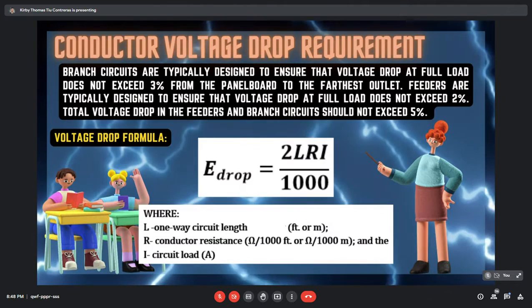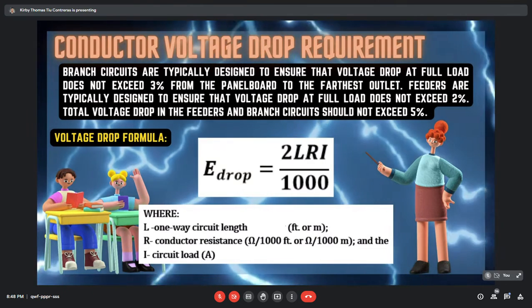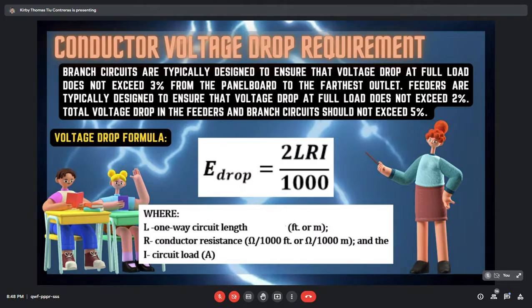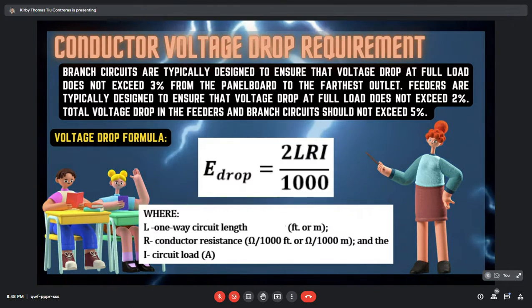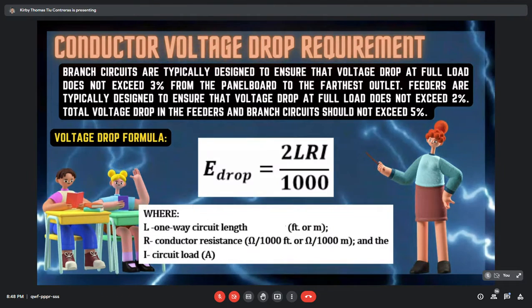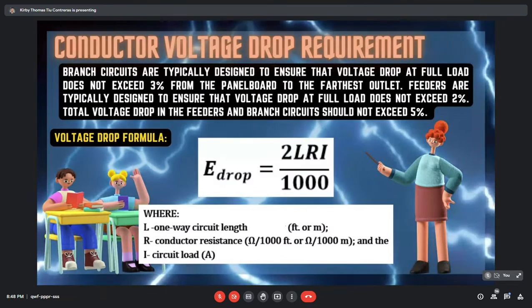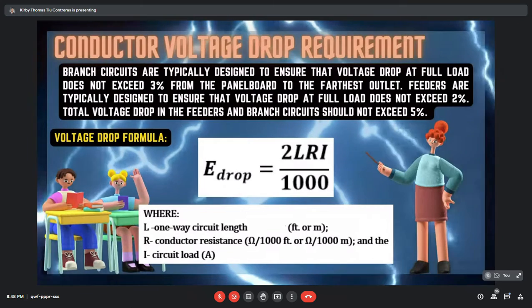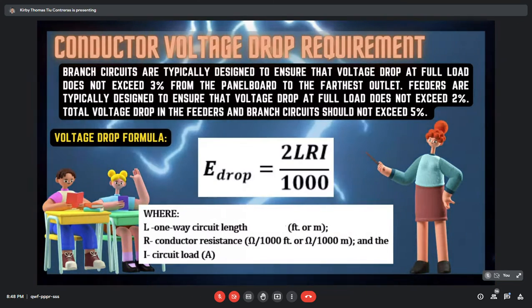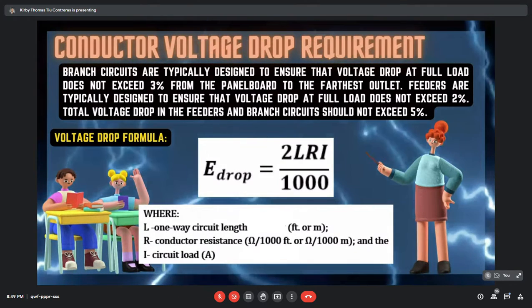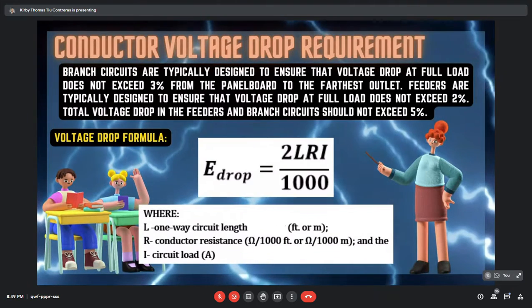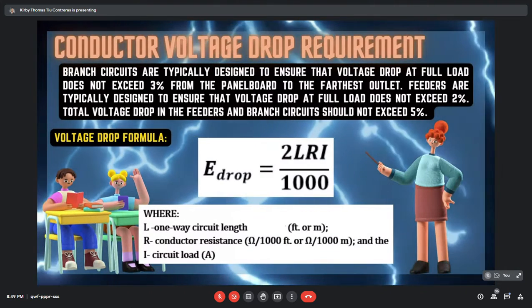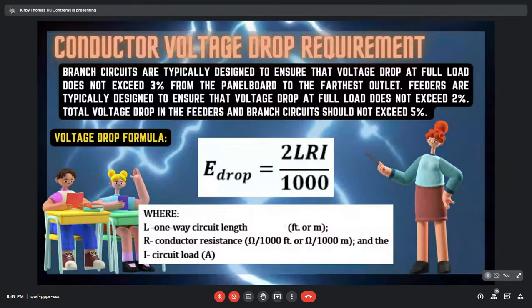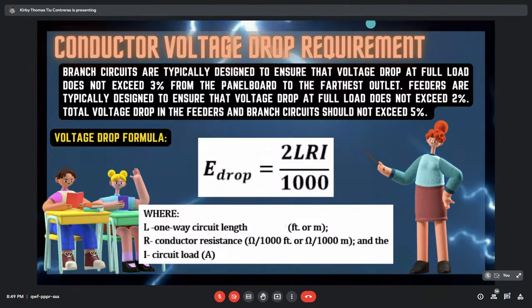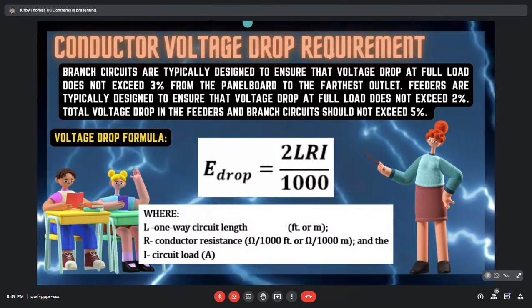So this is the basic formula in determining the voltage drop. E drop is equal to 2 times L times R times I all over 1,000, where L is the one-way circuit length in feet or meters, and R is the conductor resistance in ohms per 1,000 feet or ohms per 1,000 meters, and I is the circuit load in amps. So let's have an example. Next slide, please.